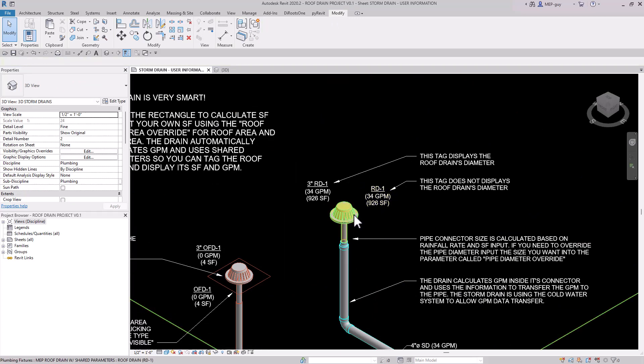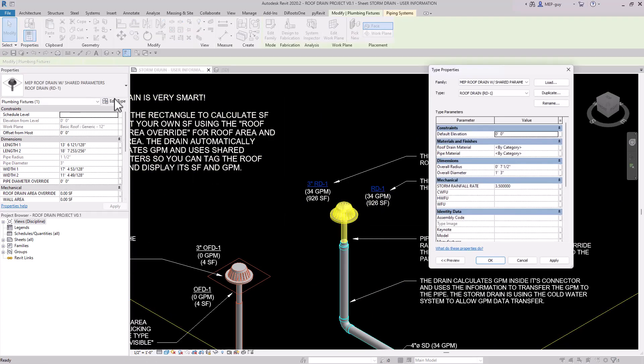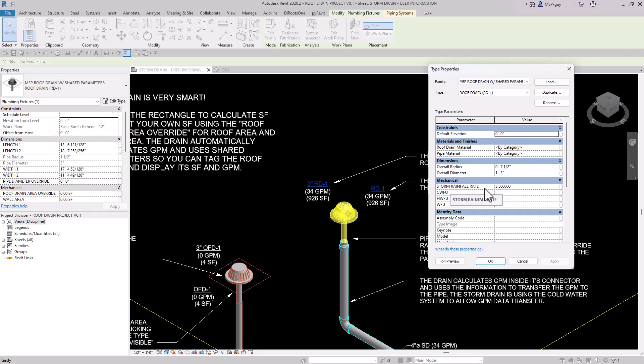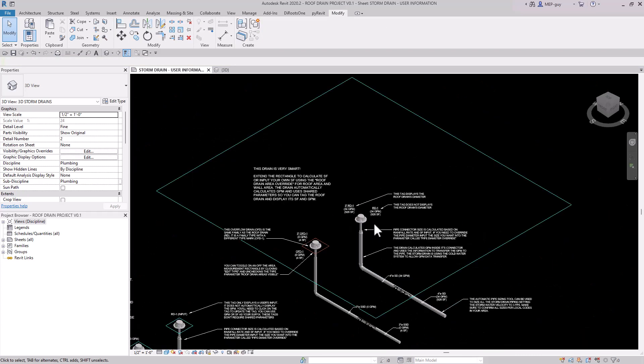The way GPM is calculated is based on the rainfall rate. If we click on the storm drain and hit Edit Type, you can see a parameter called storm rainfall rate. That depends on your area — you'll want to look it up in the International Plumbing Code based on a 100-year storm. In my area it's 3.5 inches per hour.